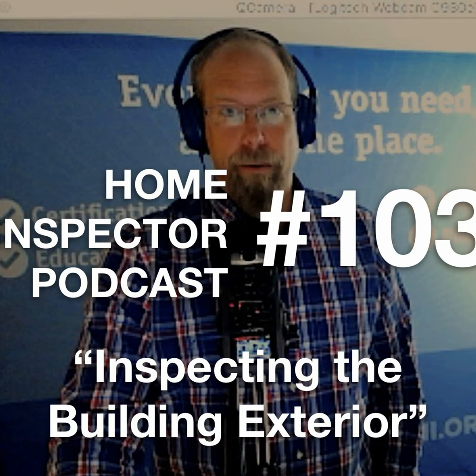And there's some flashing rubber sealant. And this is a basement door, steel doors going down to the basement. All receptacles on the outside need to be GFCI protected. So I'll have one of these. This is my main exterior tool, a GFCI tester. And here's the other tool, a screwdriver, so you can probe around. Now where a deck attaches to the house, I'm going to look for ledger board flashing details. Look at the slider door here. Look at the fastening of the deck or stairs to the house.